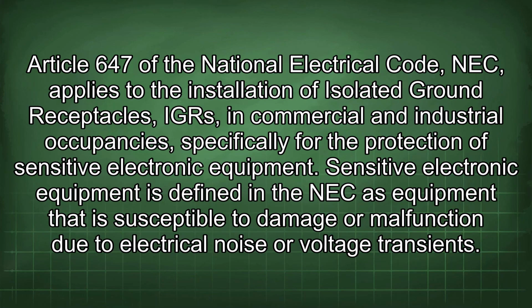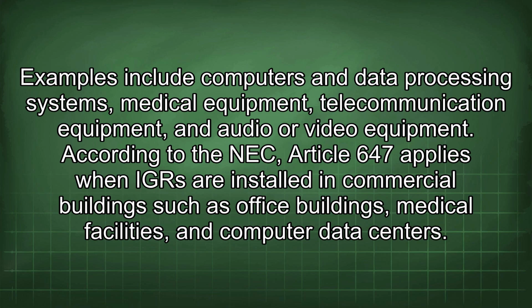Article 647 of the National Electrical Code, NEC, applies to the installation of isolated ground receptacles, IGRs, in commercial and industrial occupancies specifically for the protection of sensitive electronic equipment. Sensitive electronic equipment is defined in the NEC as equipment that is susceptible to damage or malfunction due to electrical noise or voltage transients. Examples include computers and data processing systems, medical equipment, telecommunication equipment, and audio or video equipment.